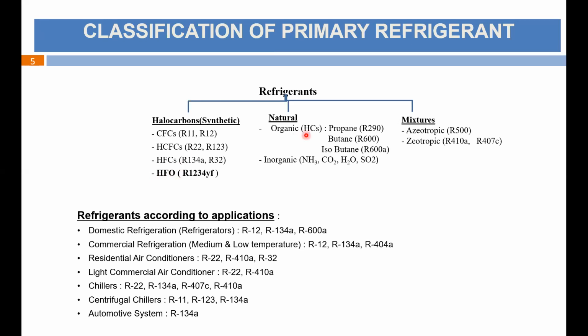And next is natural refrigerant. Natural refrigerant again can be classified in organic and inorganic. Organic refrigerants, the natural refrigerants, are all hydrocarbons, HCs. Hydrocarbons are propane, butane, isobutane. These are all organic refrigerants. And inorganic refrigerants are those which are not hydrocarbons, that are mainly different types of gases. They're like ammonia, CO2, H2O, SO2. These are all inorganic refrigerants. Even air is also an inorganic refrigerant.